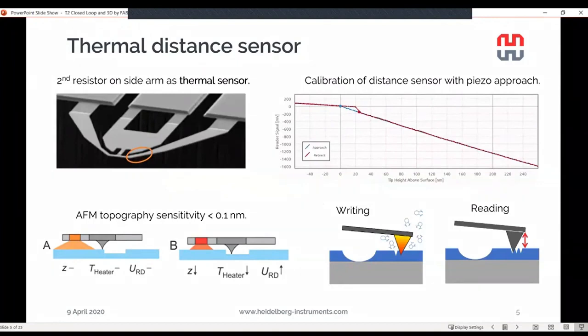Namely, when you get closer with this heater to the sample surface, you reduce the thermal resistance between this heater and the sample surface, and then you increase the heat flux, and this heater will change its temperature slightly, which you can detect by detecting the change of the resistance, which is temperature dependent. And this integrated sensor allows us to have a topography feedback with an accuracy of less than a nanometer, down to 0.1 nanometers. So imagine you are scanning and then you go into a pocket, your heater/sensor gets closer to the surface, and we can detect that.